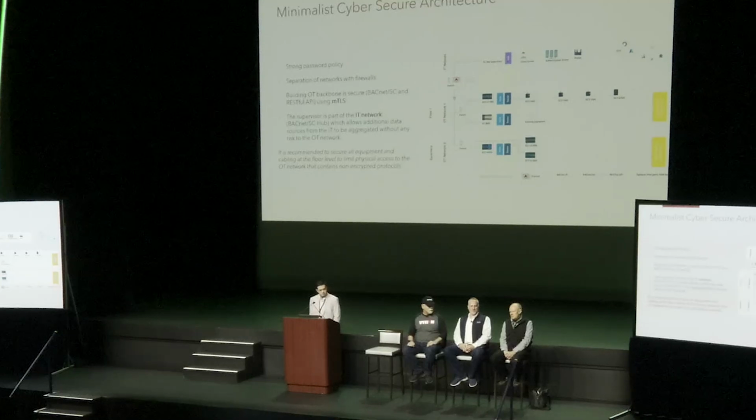So a hybrid approach is highly recommended. IP and MSTP won't fly for going up to the secure enterprise. And SC is very good for the secure enterprise, but it presents complexities and some issues that have to be addressed. If you get that purchase order, very much you should try and say, how much SC do we really need? Do we need it for the enterprise? And think about a hybrid approach.